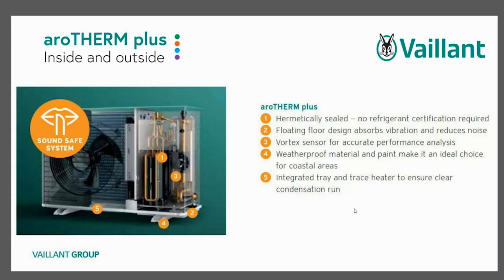It's designed for coastal applications, has a C5 rating, so a very, very high rating for salt spray. And it has integrated trace heaters in the bottom. So in cold climates where you can get a lot of water freezing in the bottom, it makes sure that doesn't happen.